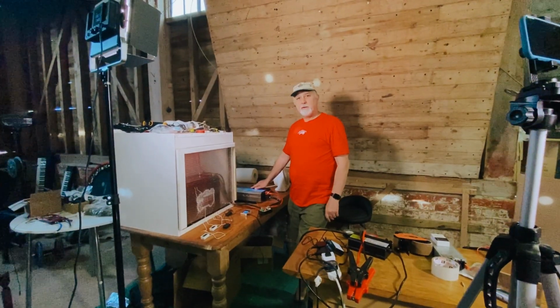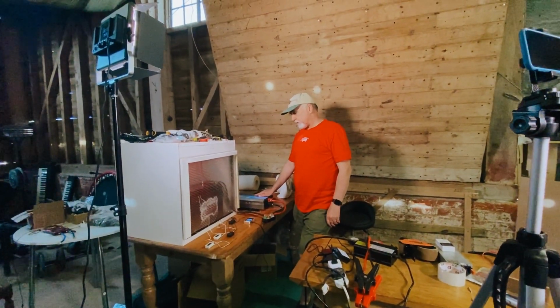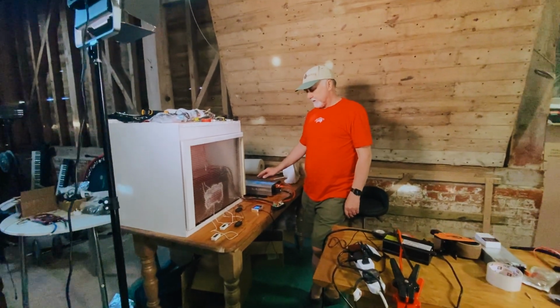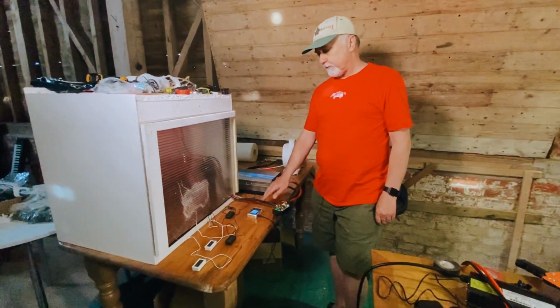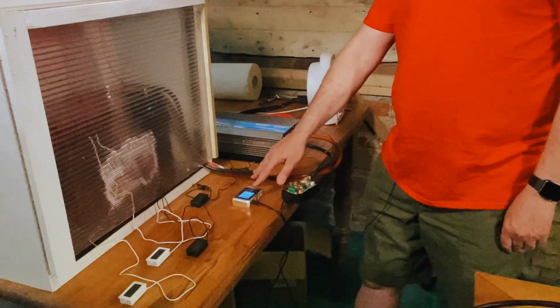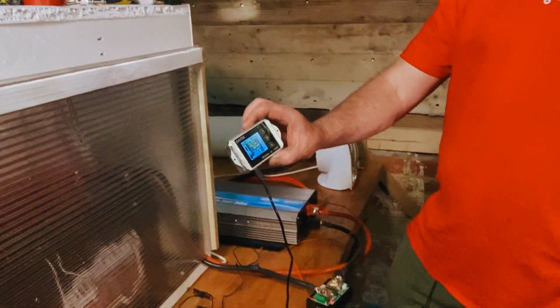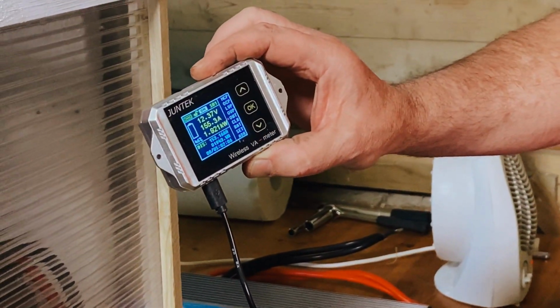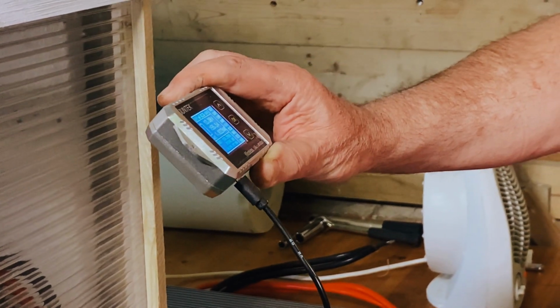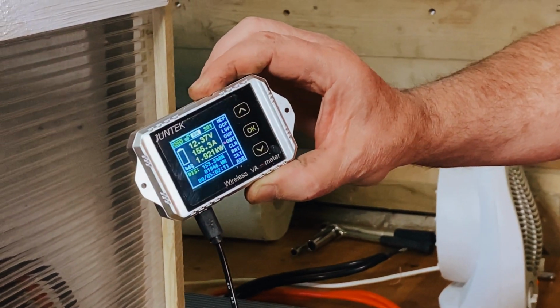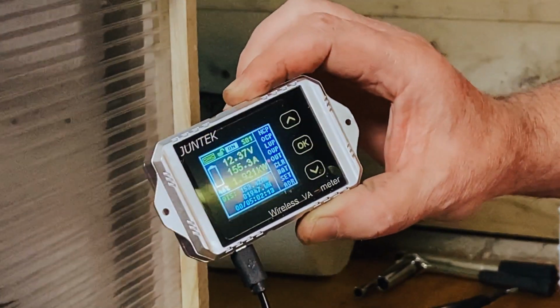We've been running for an hour at 155 amps now. Started off at about 153, 154, it's moved to 155.3 just due to voltage drops. So we've dropped very, very slightly. As you can see, we're at about 46% state of charge, so used just over half of the battery.